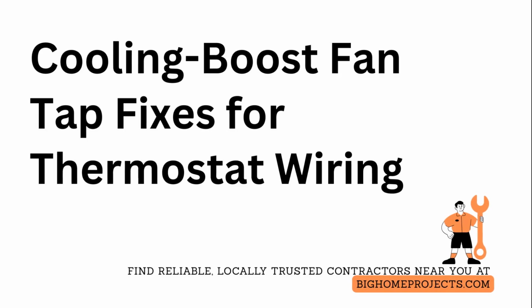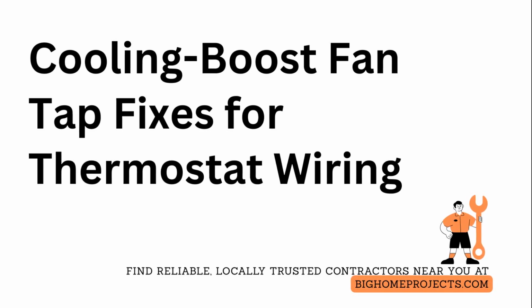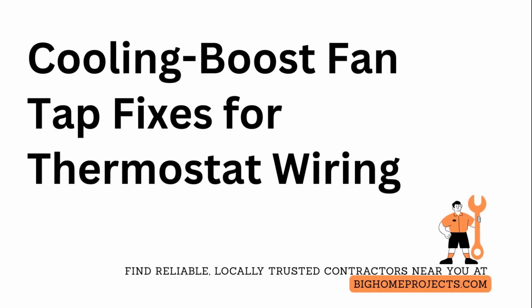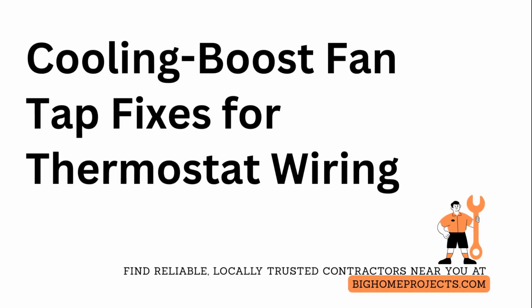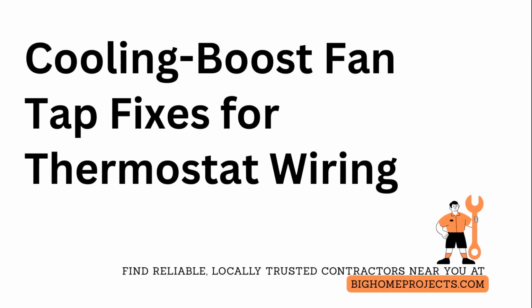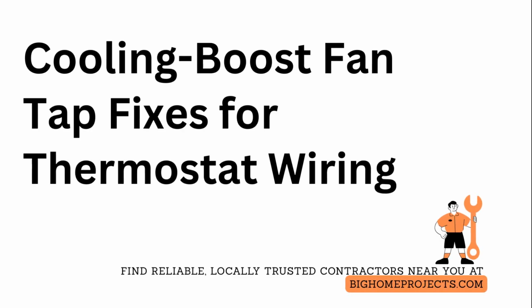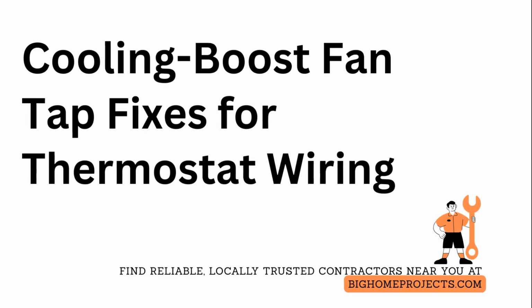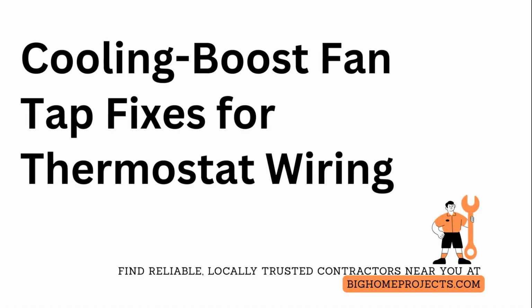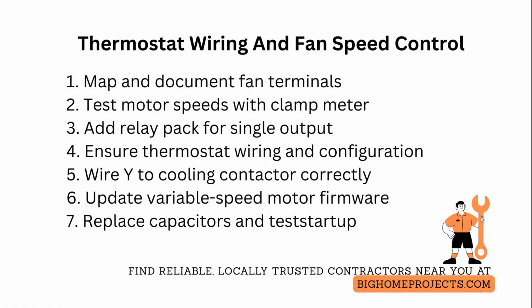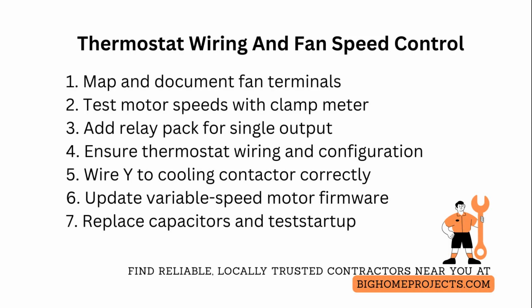Thermostat wiring and fan speed control boards differ, so the cooling fan uses higher speed terminals for efficient heat transfer, while the heating fan uses lower speed terminals for comfort, and the thermostat selects them automatically via the cooling call or the fan relay. When wiring or replacing a control board, first map every fan speed terminal label on the board to the actual motor leads and document wire colors before disconnecting anything.